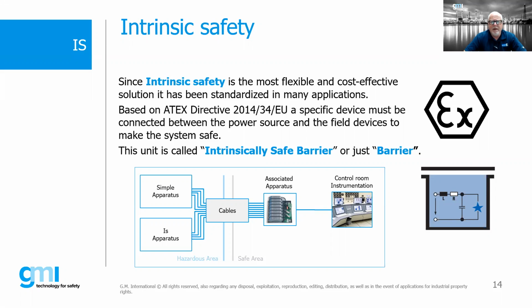Based upon the ATEX directive, a specific device must be connected between the power source and the field device to make the system safe. We call it an intrinsically safe barrier, or a barrier, though we use the term loosely. It could also be called an associated apparatus. A Zener barrier or a galvanically isolated barrier is considered to be an intrinsically safe barrier.